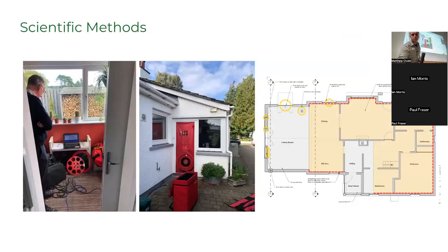time. Now, what we do in my practice is a scientific approach. So we execute blower door tests on as many projects as possible, because you don't need to rely on it being a windy day. Then you can go around the building while the fan's running.